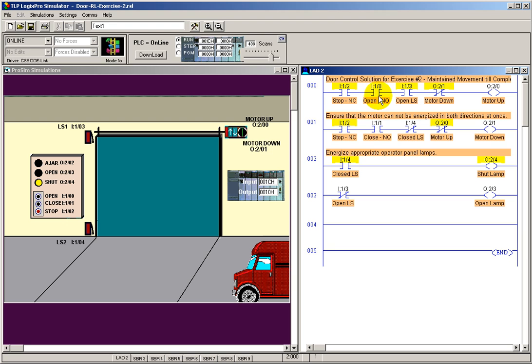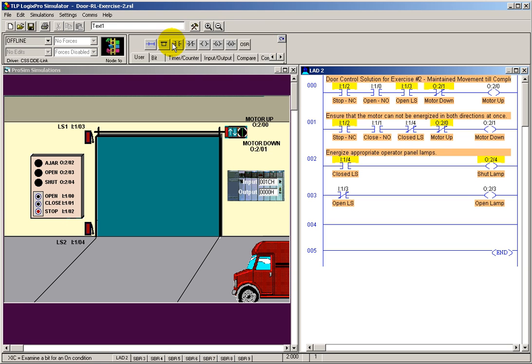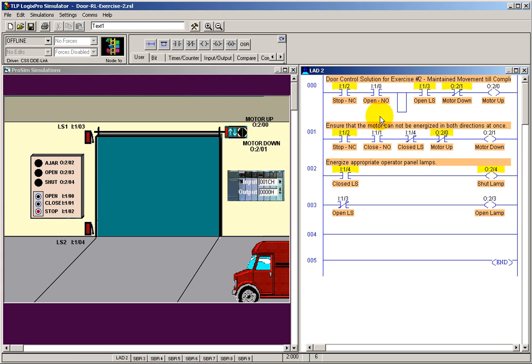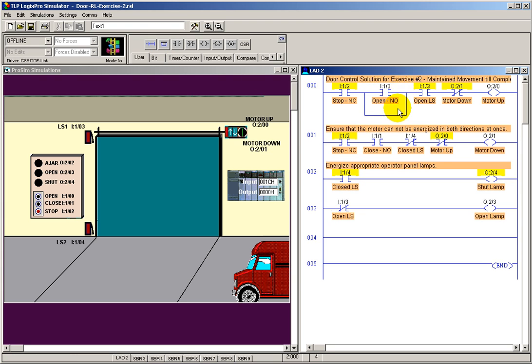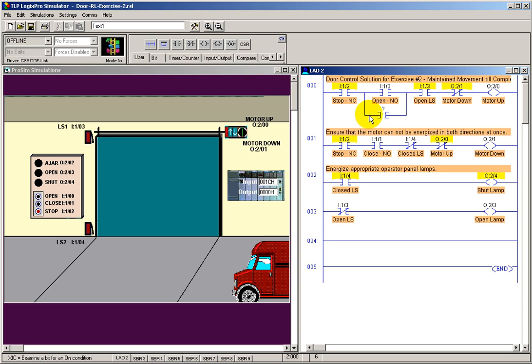Secondly, let's seal in the open and close switch. To do that, we're going to have to add a branch. Let's go back to the program mode. Find our instructions here and put a branch in around our normally open up switch. And we're going to put an instruction set here. Examine if closed. And our seal in, pretend there's some auxiliary inputs. It's similar to having auxiliary contacts on the motor up motor.